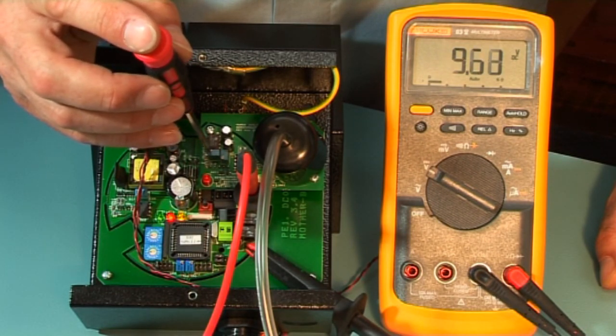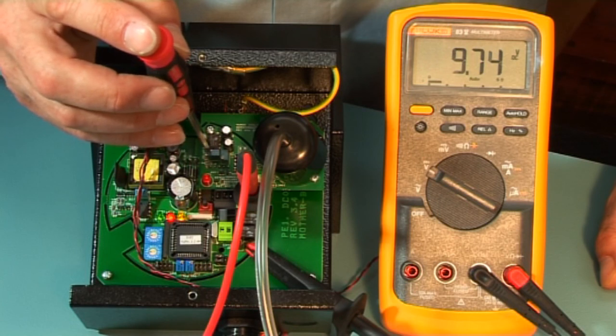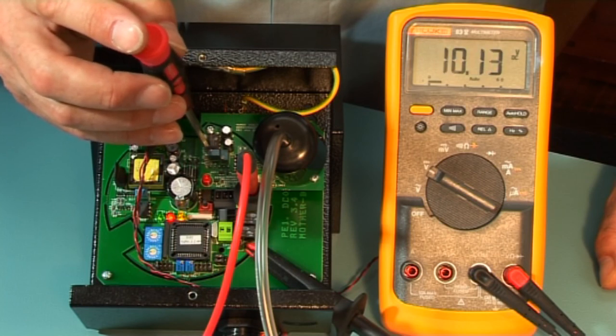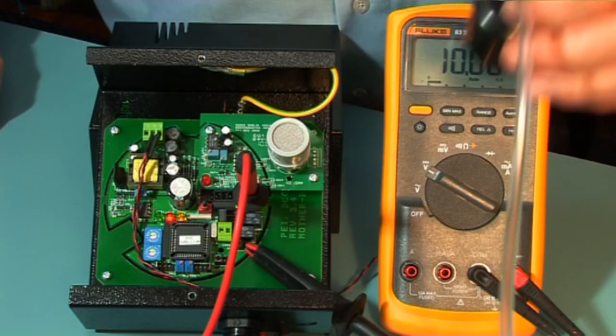If connected to the ST-MON, the panel will show the output for the sensor on the display and will activate its relays as set in the panel. Remove the gas and the unit will come out of alarm and return towards 0 volts.